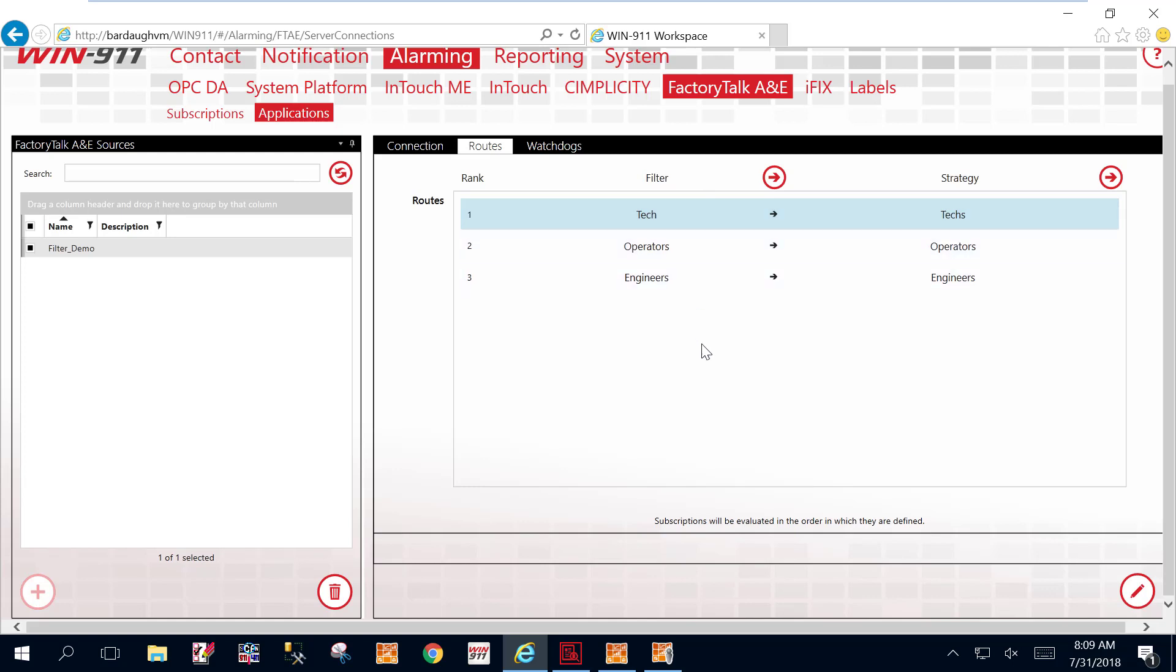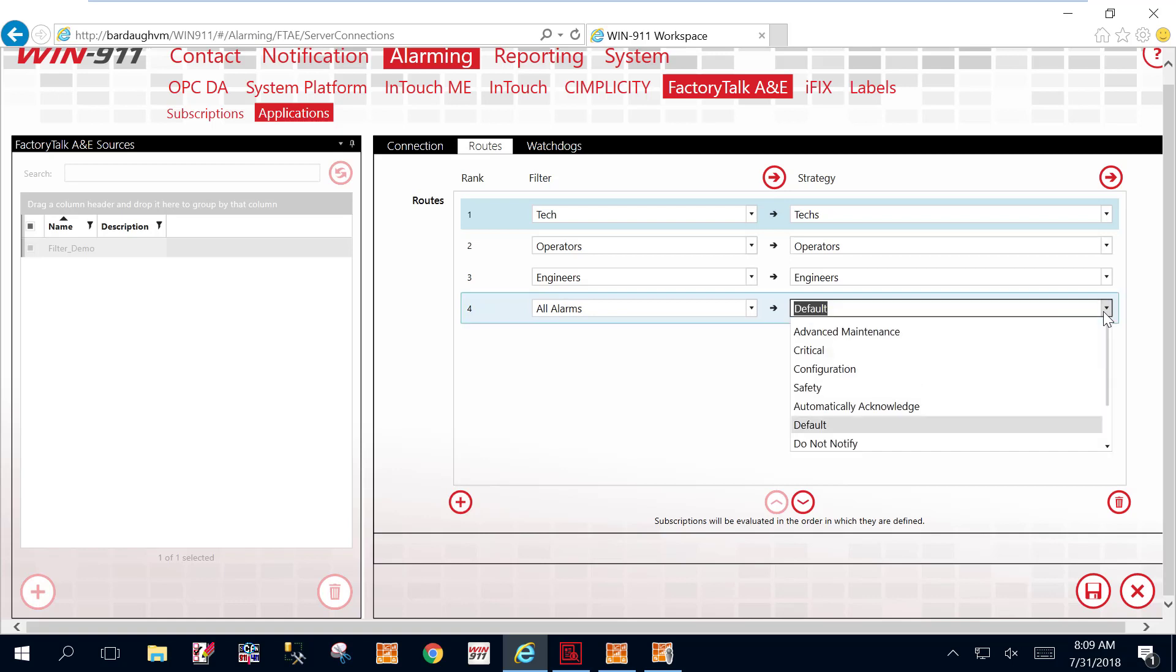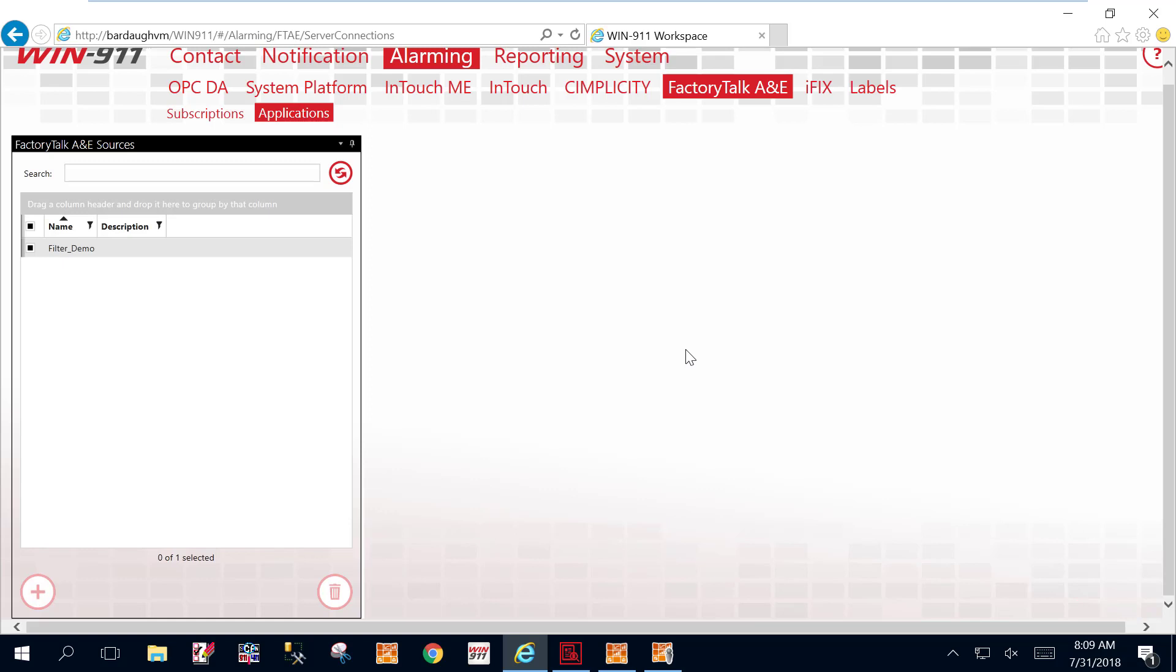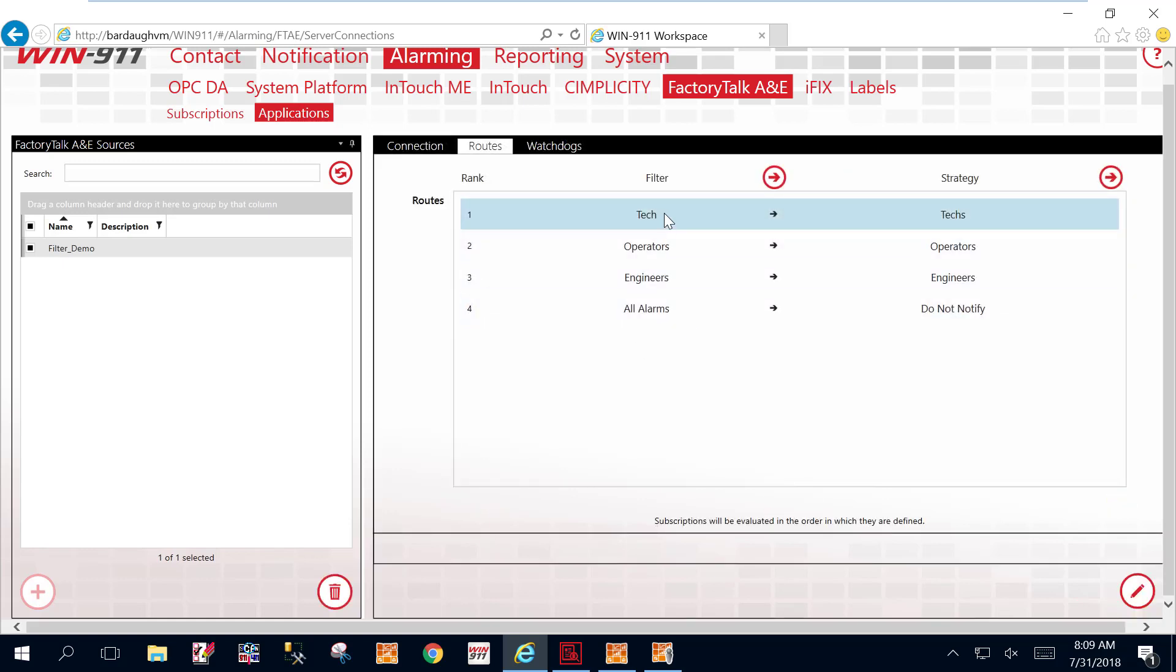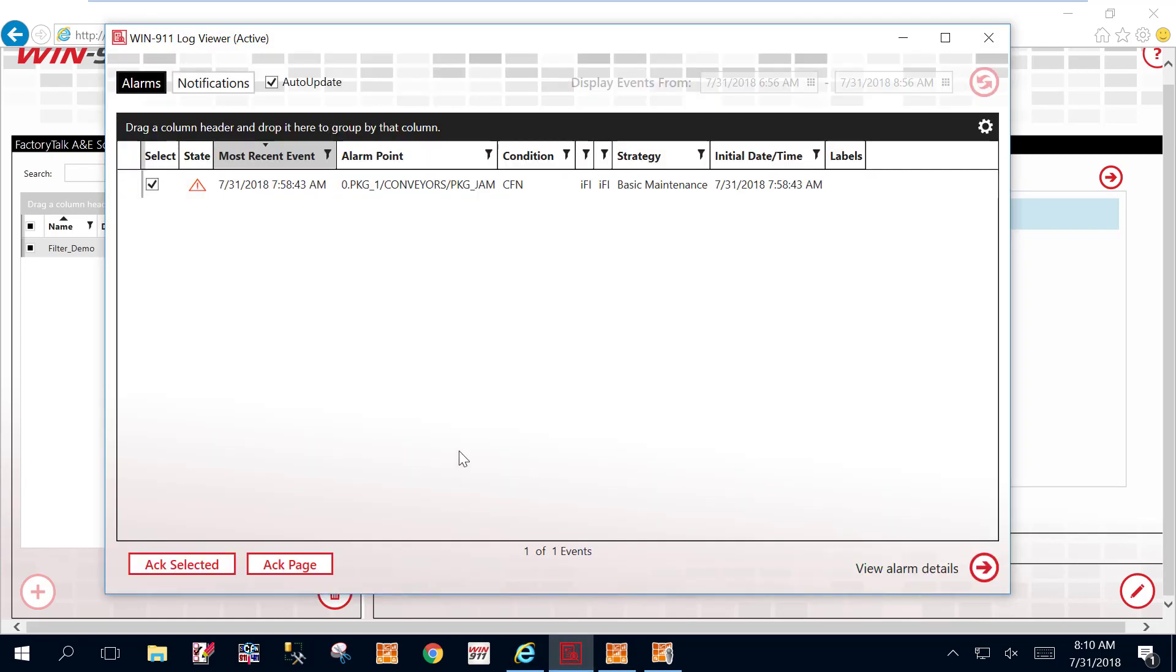Now one thing during your troubleshooting, especially during your configuration process to be aware of. One item you might want to add to make sure your alarms do go somewhere and your filters are correct and you filter down the right things, you do an all alarms filter and just for troubleshooting purposes, you could do a do not notify. And why would you do this? Because what happens if you go down all these filters and your alarm isn't caught? I would recommend having it to go somewhere and do not notify is a good place for that. Because you can do some troubleshooting to know that, okay, my alarm went through all these filters. It was supposed to go to the operators filter, but maybe it didn't. Maybe you need to check your case sensitivity on some of those filters or maybe you weren't filtering on the correct thing.